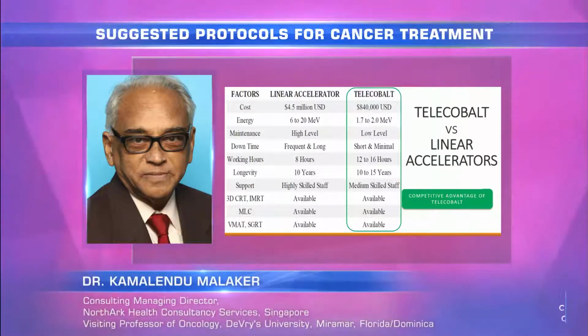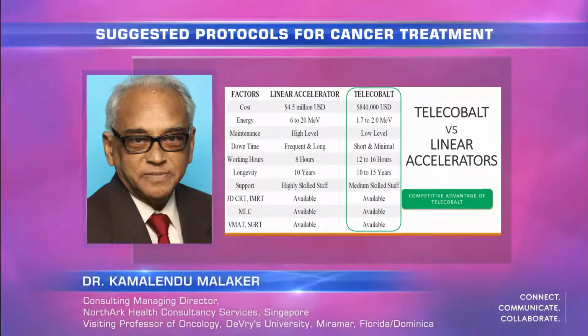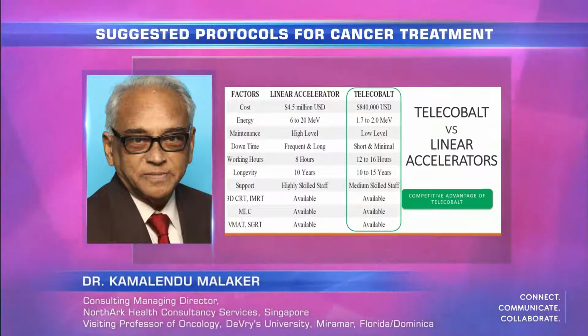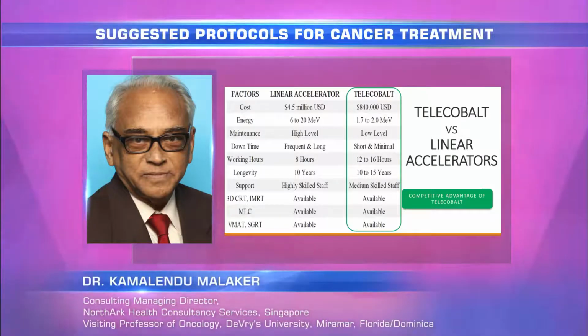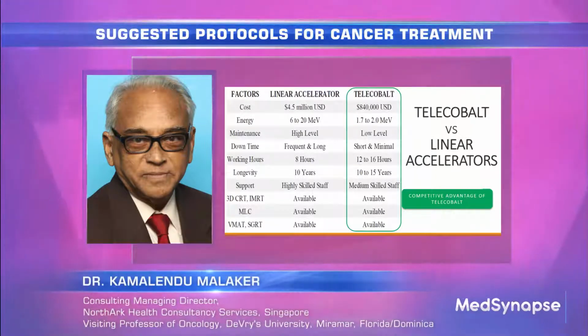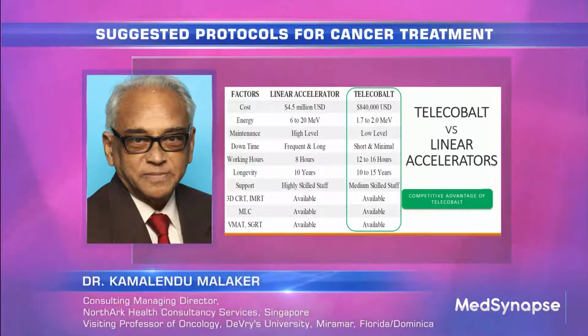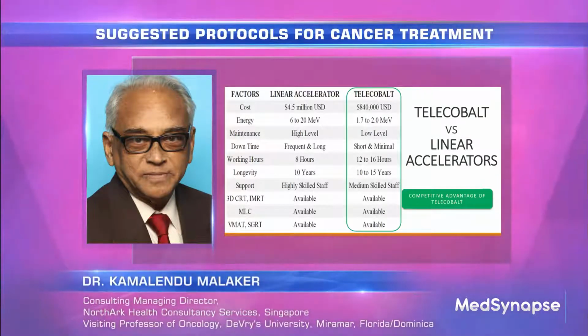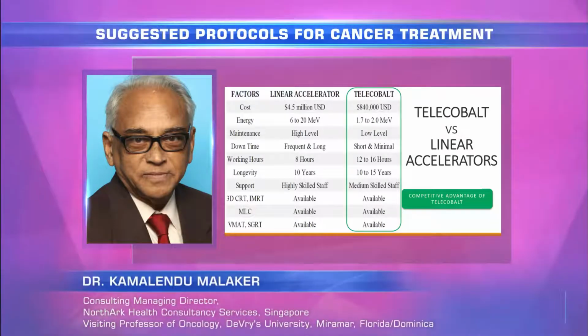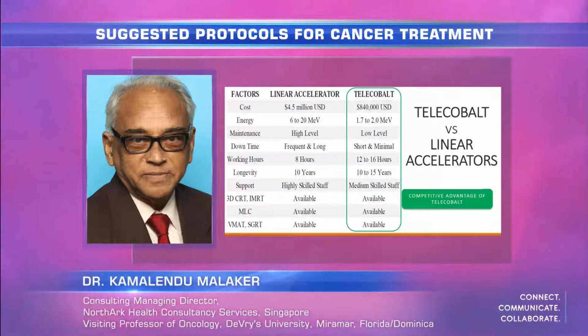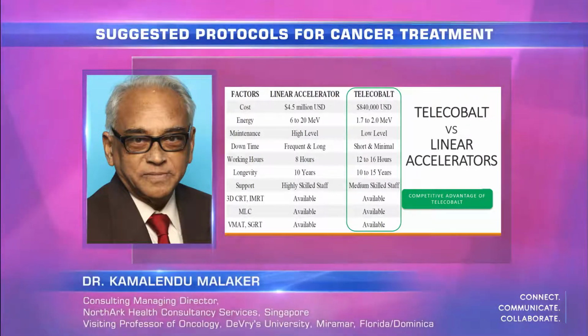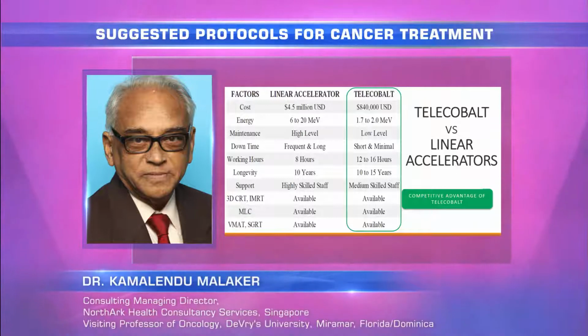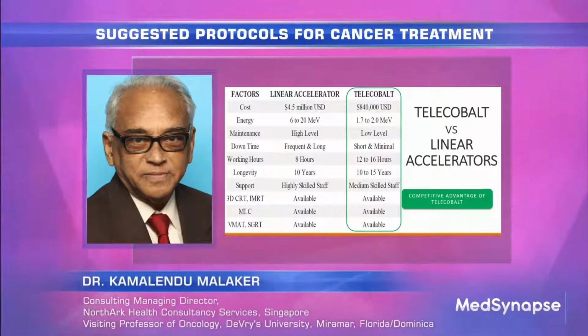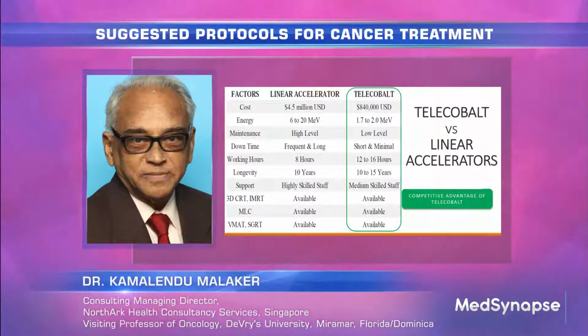Maintenance is high. Why maintenance? It has to be checked every day. A physicist must check every day before we switch it on. Telecobalt also needs to be checked, but the checking is minimal. You can work a linear accelerator only for 8 hours, but telecobalt can go for 12 to 16 hours. At times, when we're too much pressed, up to 18 hours when they need to do it.